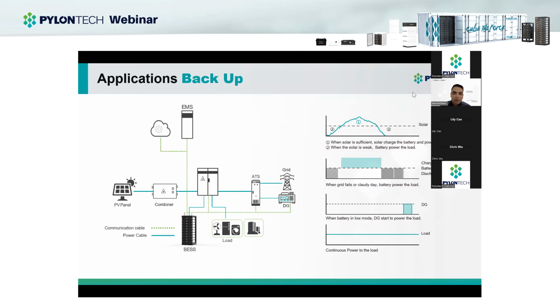But let's say we just want batteries to discharge when we have a grid failure. The batteries will be in standby mode all the time, but if the grid goes off, or if we don't have solar production, let's say we just have grid and batteries, the grid will charge the batteries and keep them charged. But if the grid fails and goes off, the battery immediately enters the system and powers the loads.